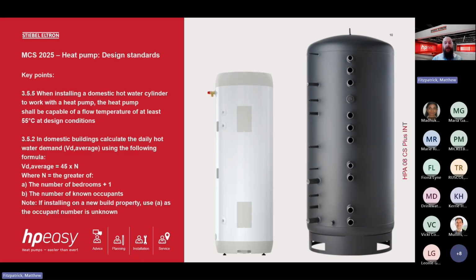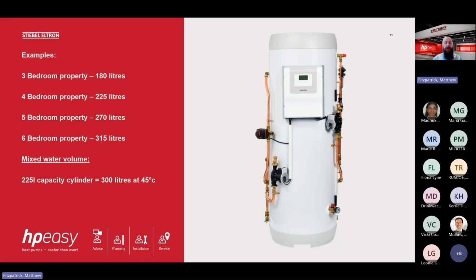So taking some of the design standards, we'll just have a look at potential cylinder sizes for various size properties. So a 3-bedroom property, as I've mentioned, is 180 litres. A 4-bedroom property is 225 litres. A 5-bedroom property is 270 litres. And a 6-bedroom property is 315 litres. Now, this will all depend on the property. This is a rule of thumb.